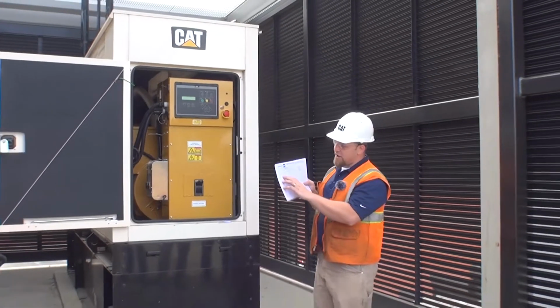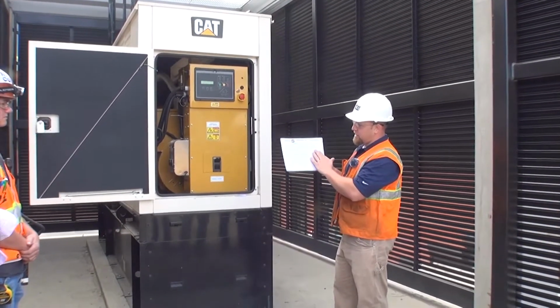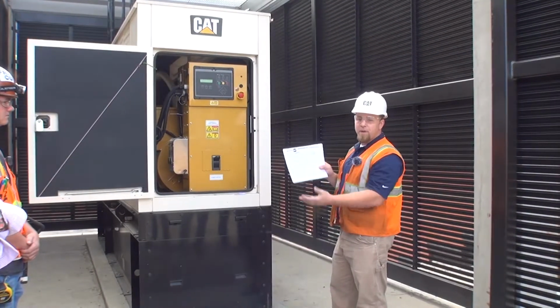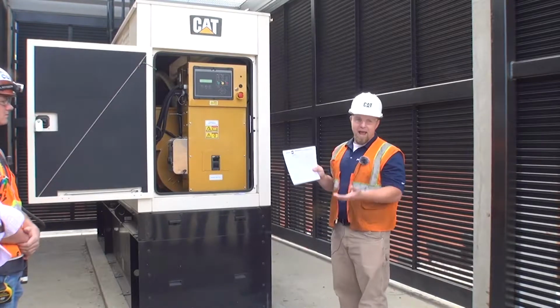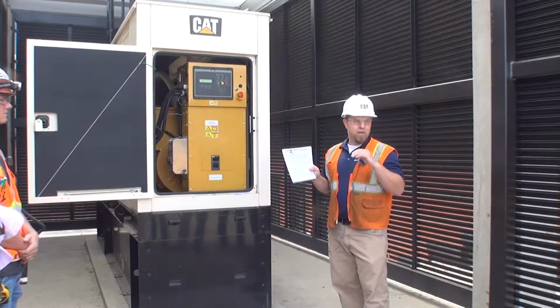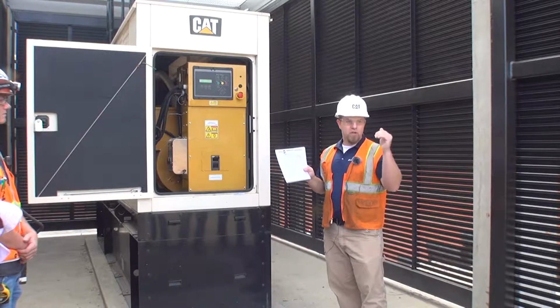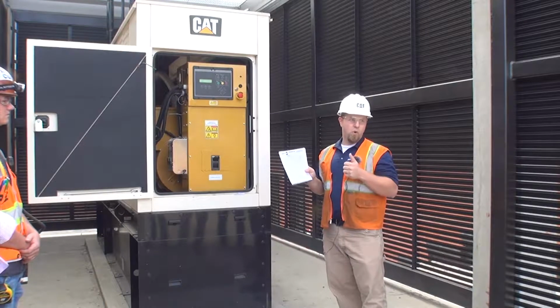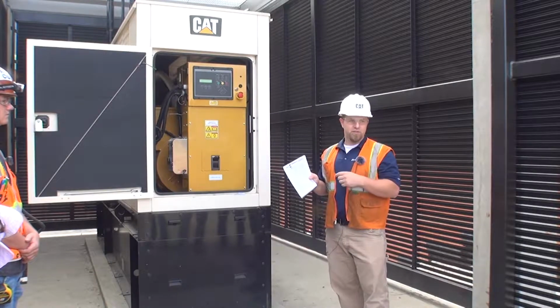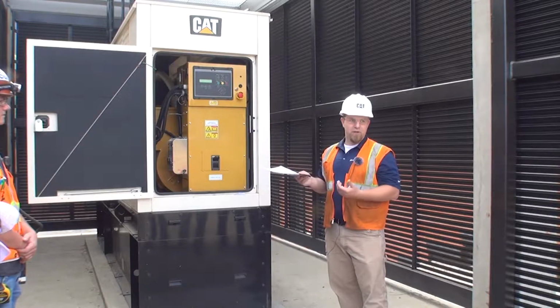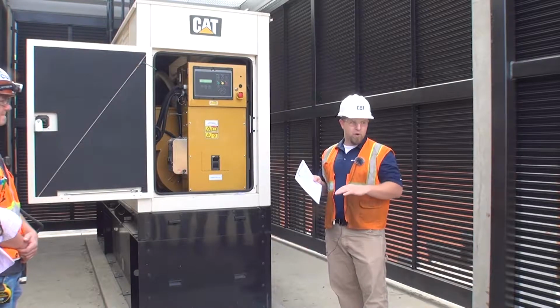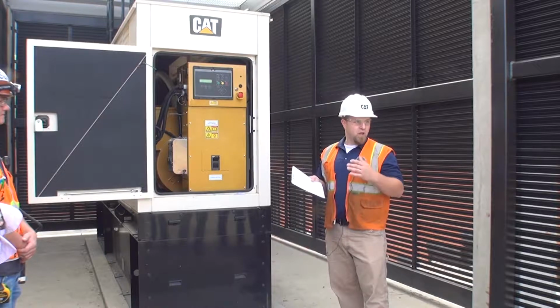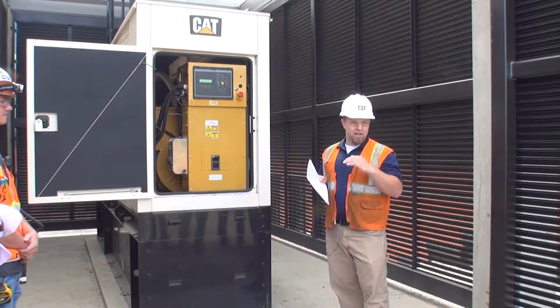So kind of going down the list, we set it up really easy. Fuel, you want it to be above 75%. At 90, you're going to have a high fuel. At 95, it'll have a high fuel shut off, so it won't let you fill more than that. Those get tested during startup, and usually we'll have the alarm going off for a while until you can burn that fuel off and get it down low enough to where it's not at that 90%.